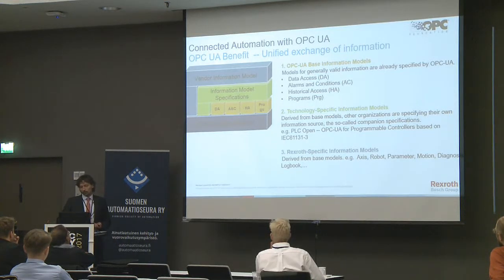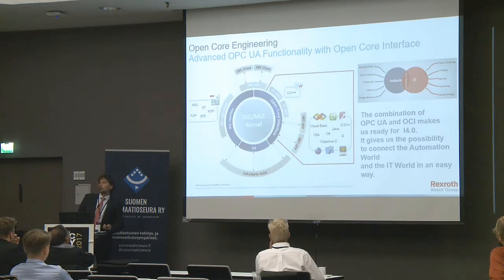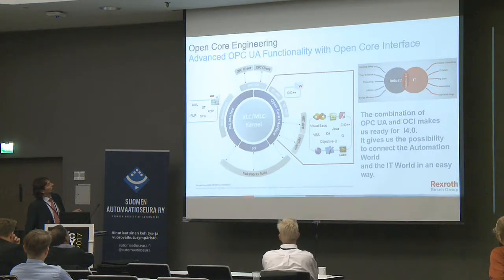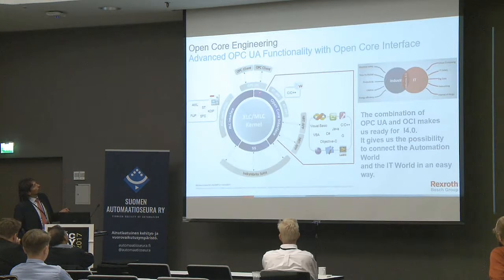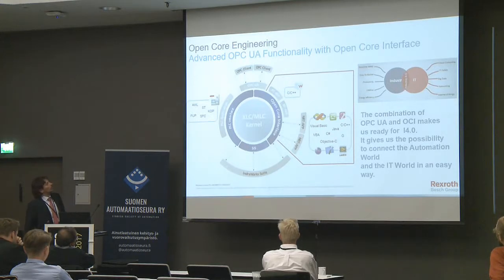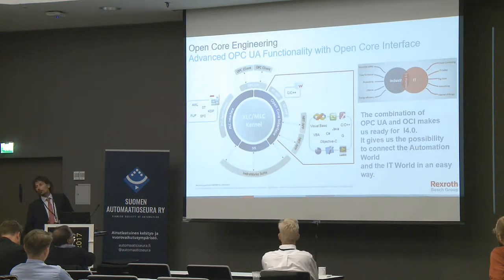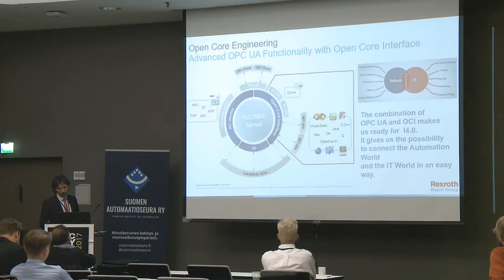The reason why we can support this wide range of Rexroth-specific information models is the way we implemented OPC UA. Normally, OPC UA has access only to the PLC interface. In our case, OPC UA also has access to our so-called OpenCore Interface. With this OpenCore Interface, we have direct access to our control kernel and can offer all the data within our control kernel without any programming in the PLC. This enables us to connect the automation and IT world in a much smarter way.